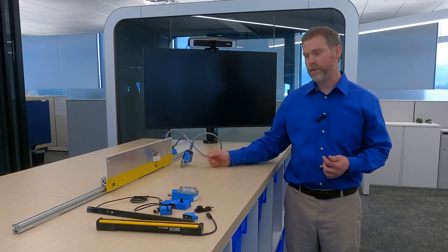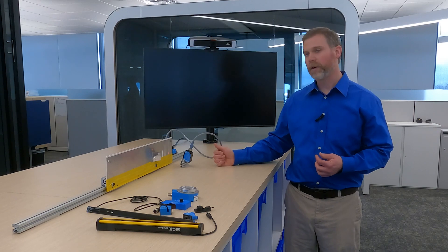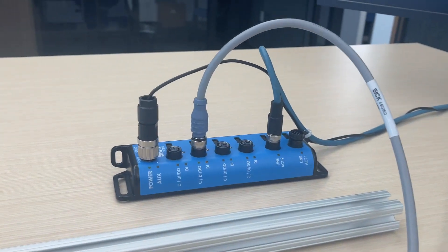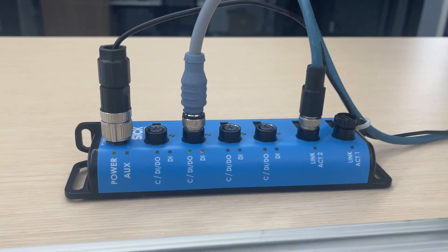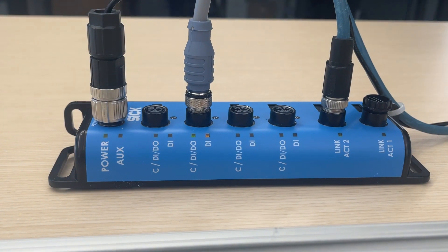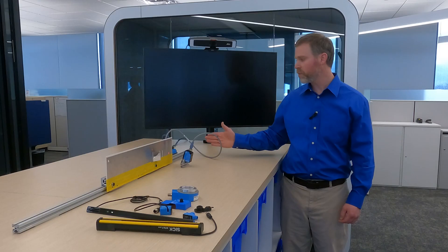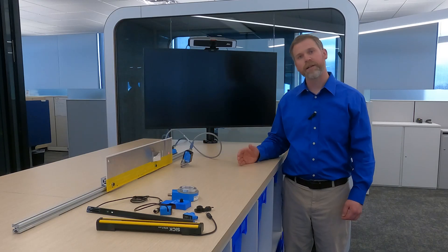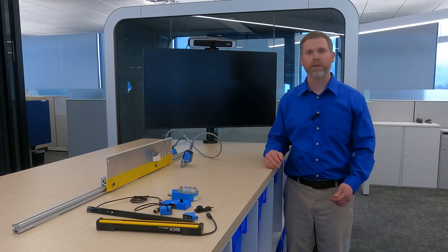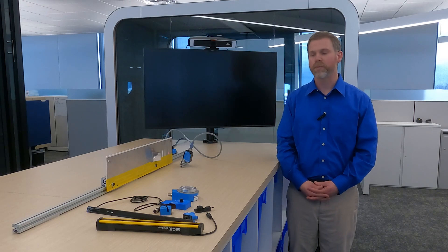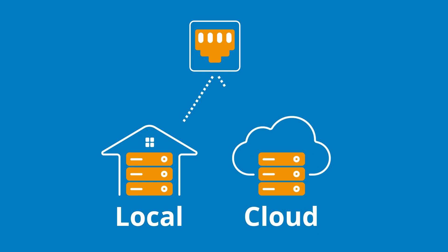The laser time-of-flight sensor takes its information over IO-Link and passes it to the second piece of the system, which is the sensor integration gateway — the SIG200. That takes the information in over IO-Link and passes it to Ethernet, so once the data is on Ethernet you can manage it locally or on the cloud.